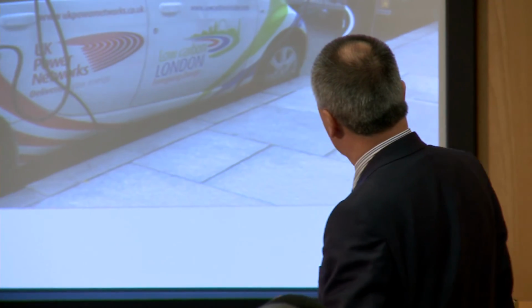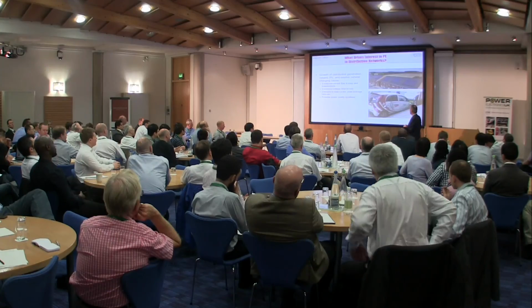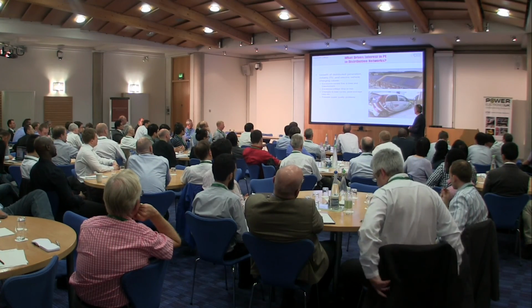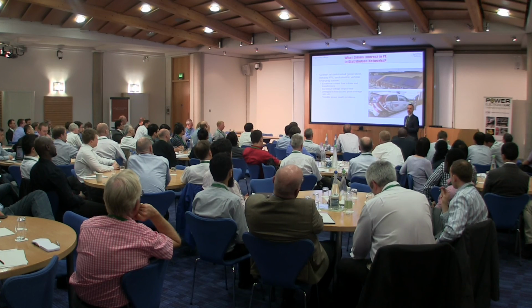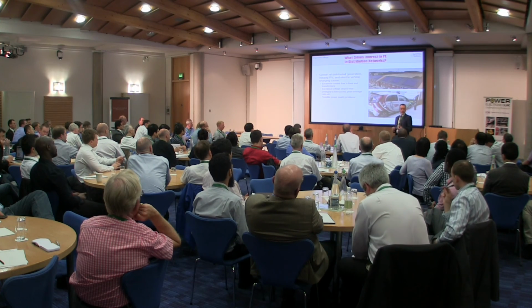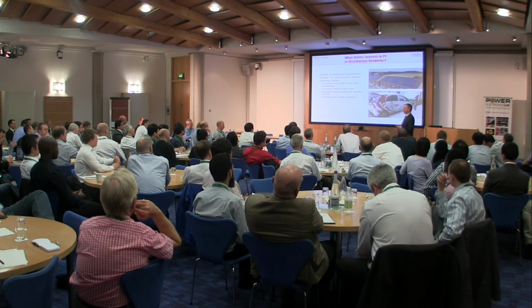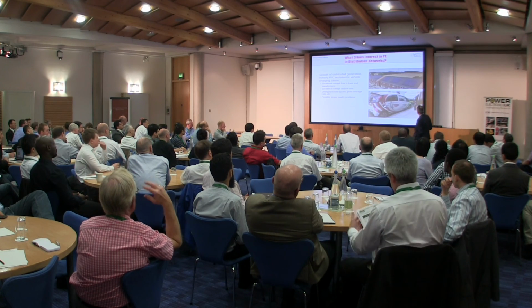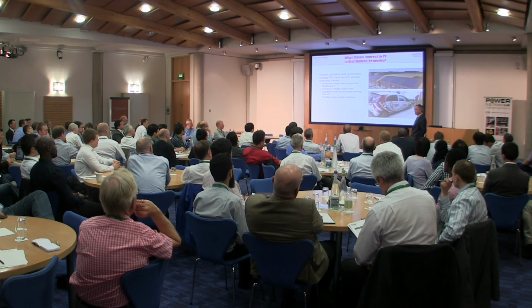The first illustration, very clear, rooftop PV, a real big push from the feed-in tariff in this country, had already got well underway in many other European countries. And in several of those countries, we're beginning to see now the first signs that voltage control is becoming problematic in distribution because of the injections of power from PV at times when demand is low.